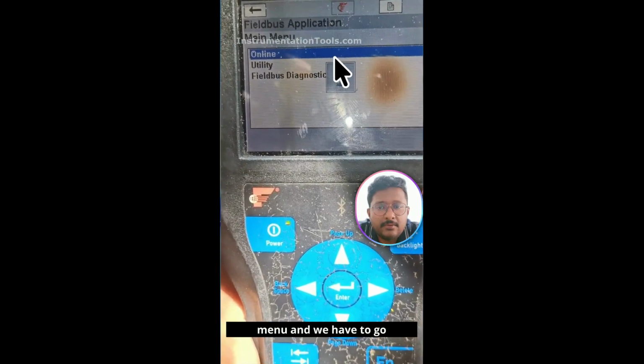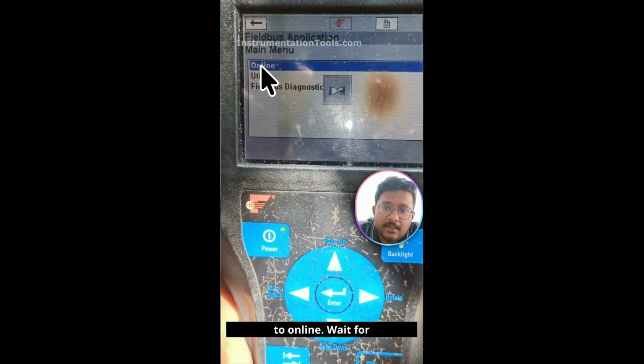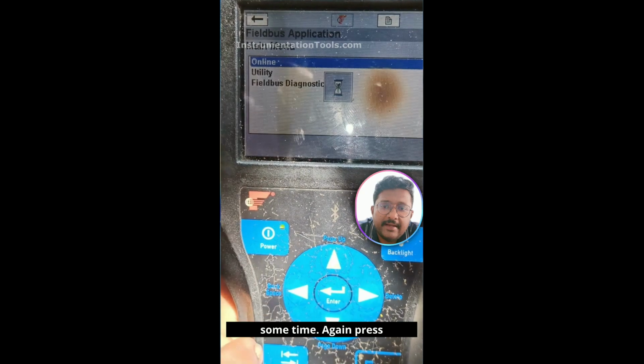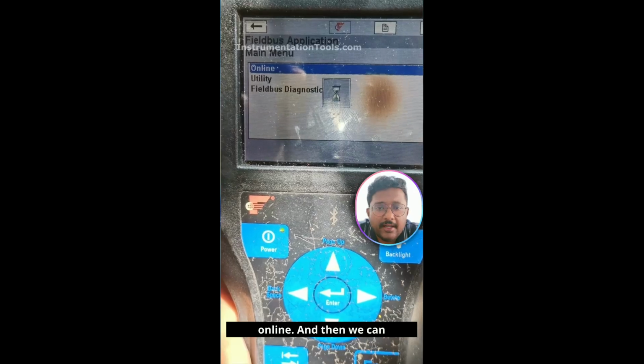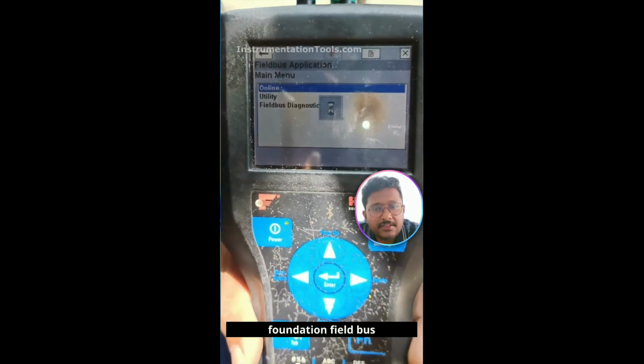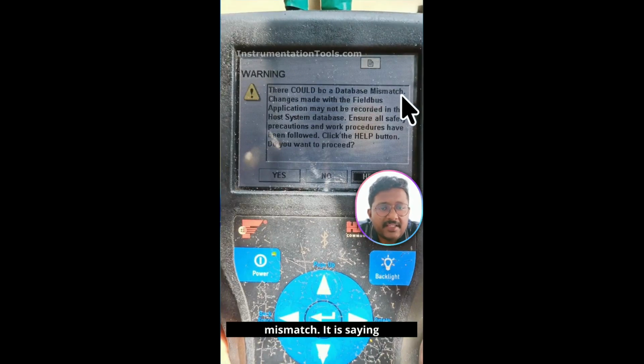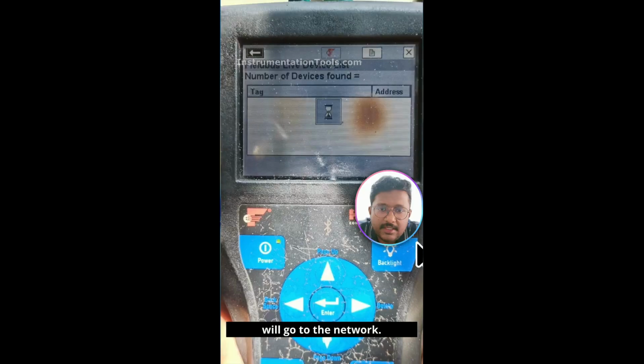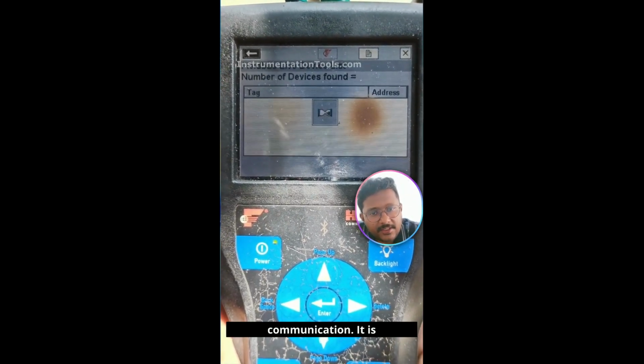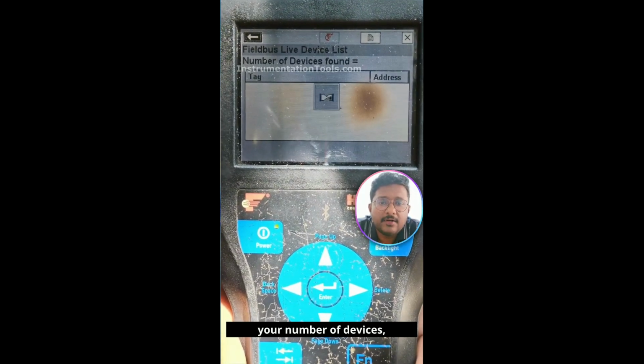This is our fieldbus menu and we have to go to online. Wait for some time. Again, press enter. We have to go to online, and then we can see the available foundation fieldbus instruments on the network or on the segment. See, there is a warning. There could be a database mismatch. It is saying that there is a database mismatch with your host system database. It is fine. You can press YES, no issue, and then it will go to the network. See, it will take some time. It is acyclic communication. It has the least priority. That means it will take time, depending on your number of devices, length of the cable, and many other parameters. Okay.